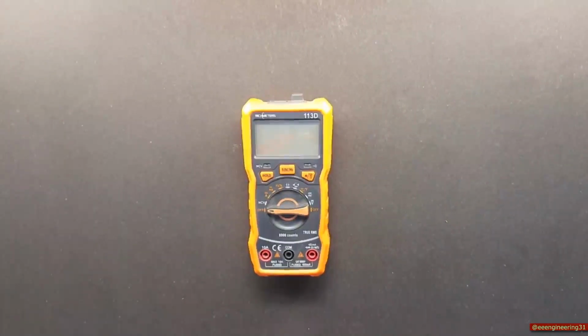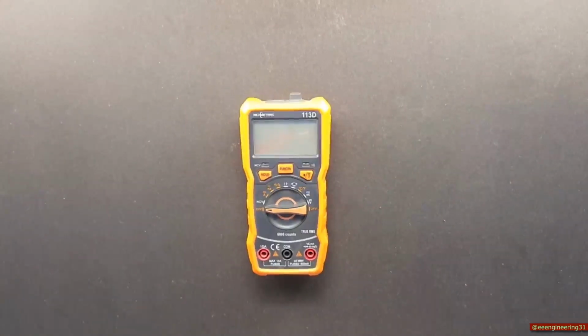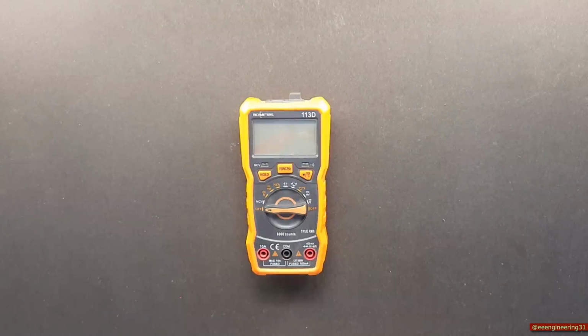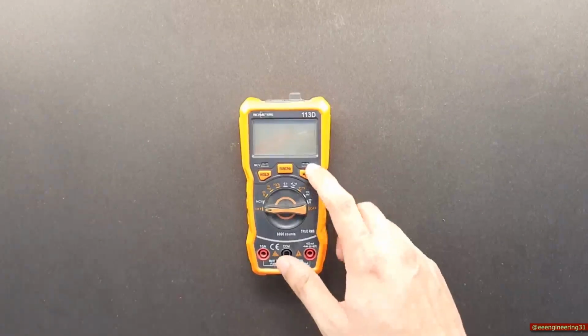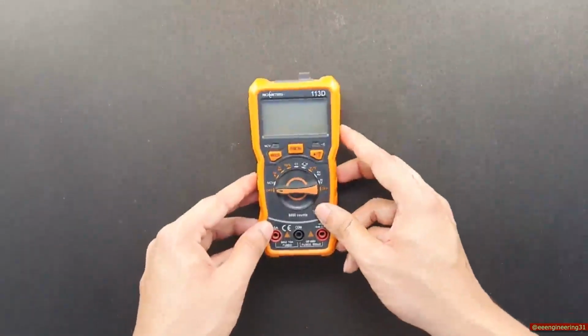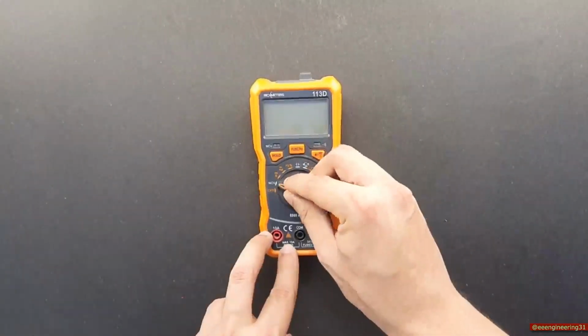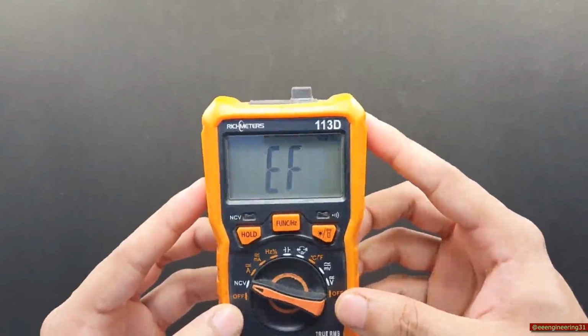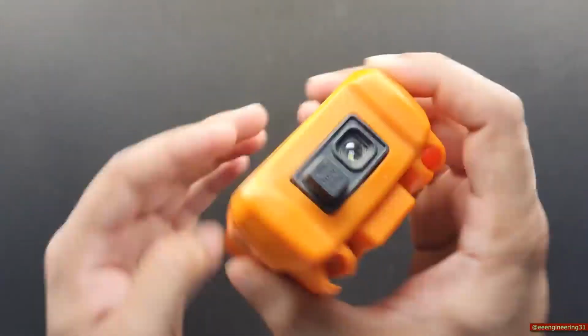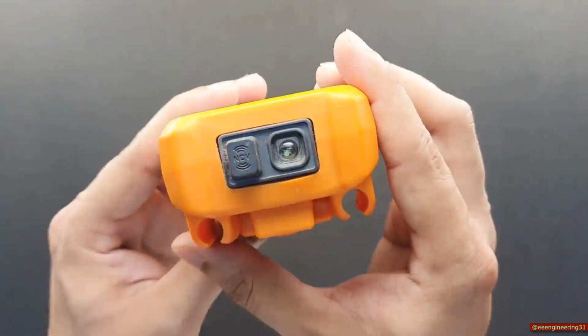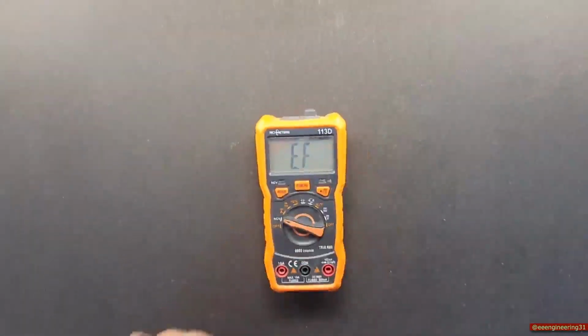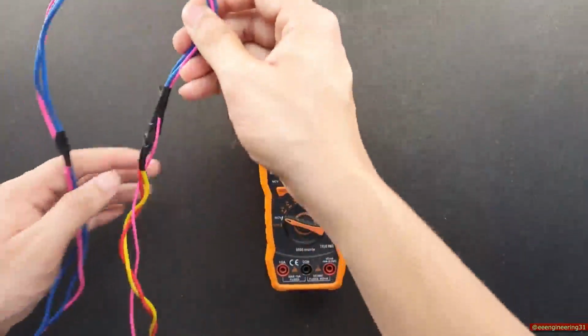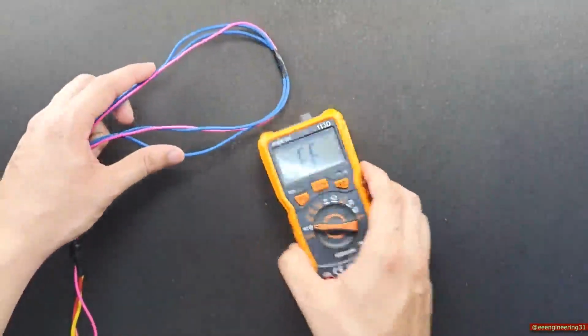The NCV stands for non-contact voltage, and it's a very useful feature if you're working with mains voltages. As the name implies, it can detect high voltages without even probing it. It measures electrical fields in the air and displays the strength with beeping sounds. We also have a light along with the audio warning. To turn it on, we don't need any probes—we just set it to NCV, and this right here is the antenna. So to use it, you can bring it near any live conductor, like this live conductor here.